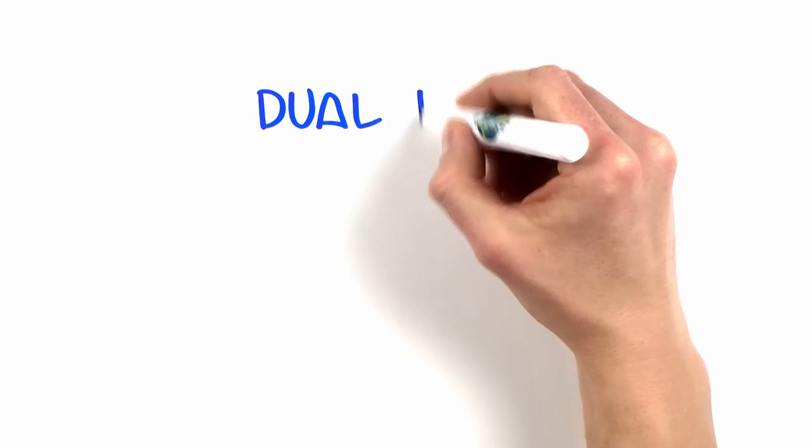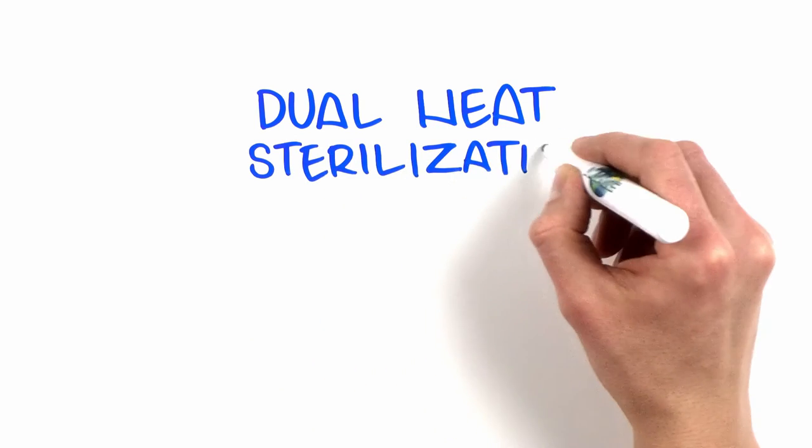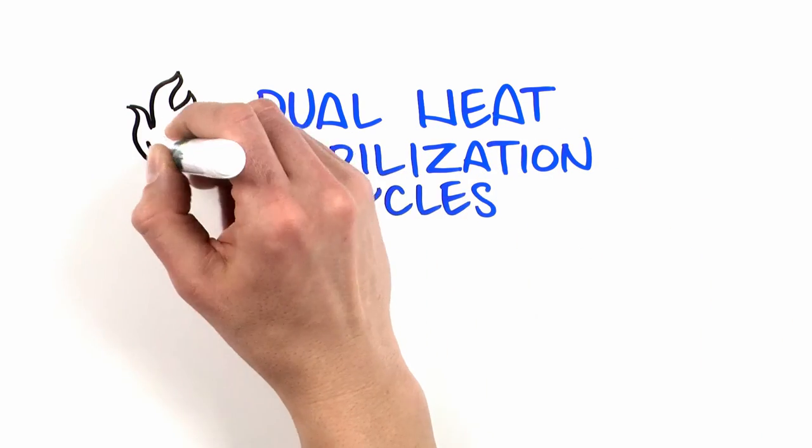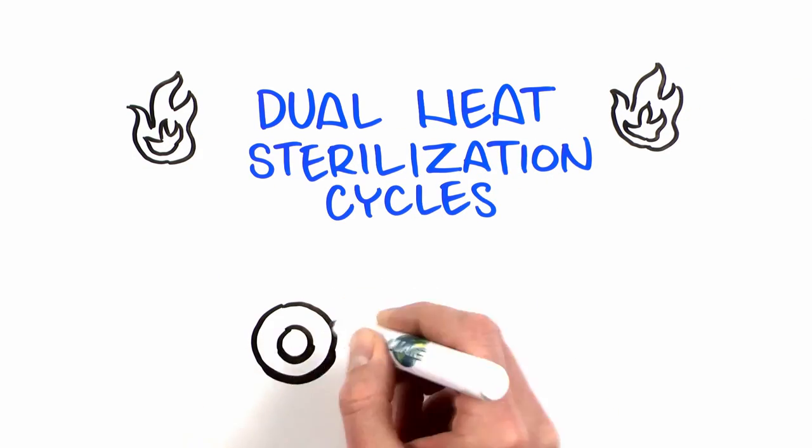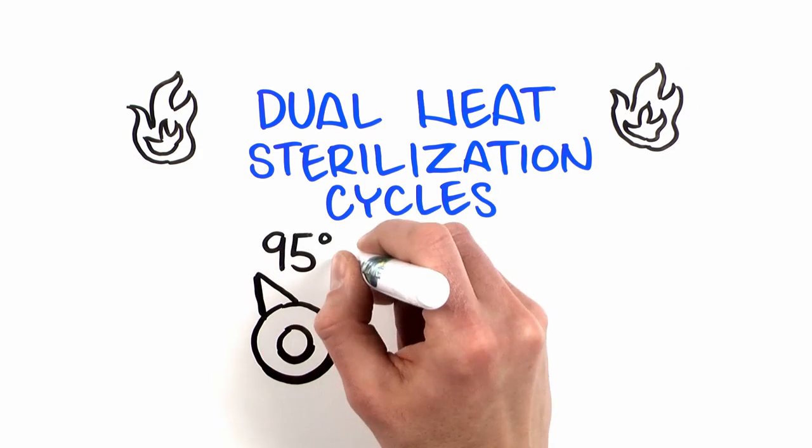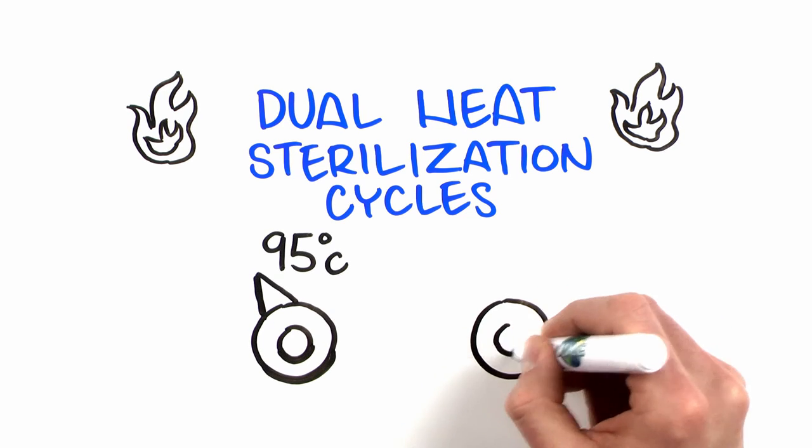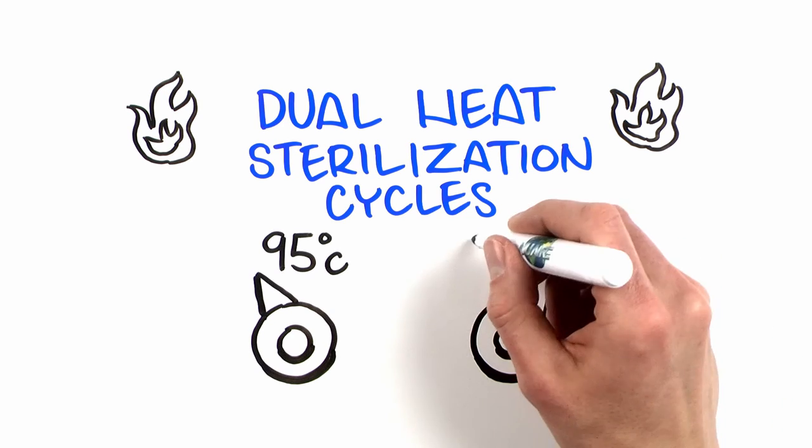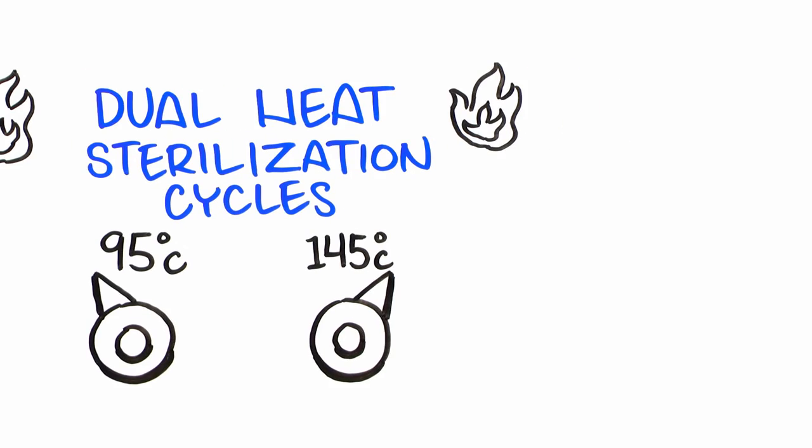New Air is one of the few offering dual heat sterilization cycles, so you can choose whether to run the 95 degrees Celsius humidified or 145 degrees Celsius dry cycle.